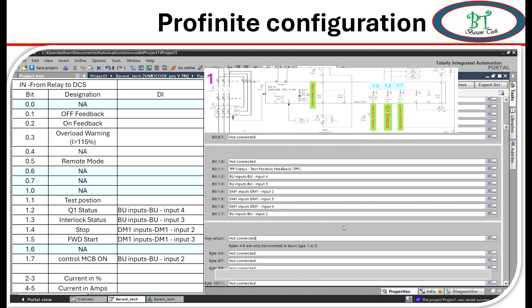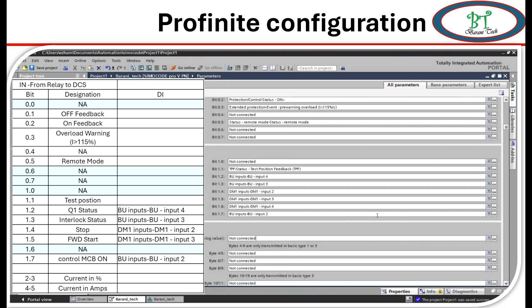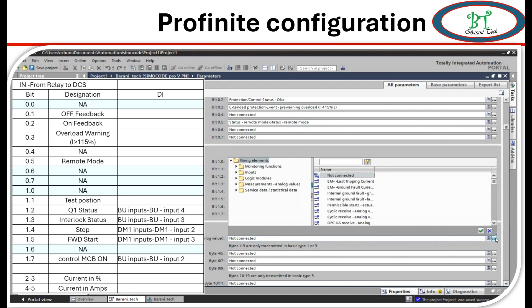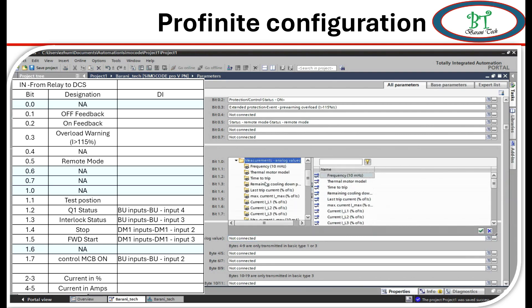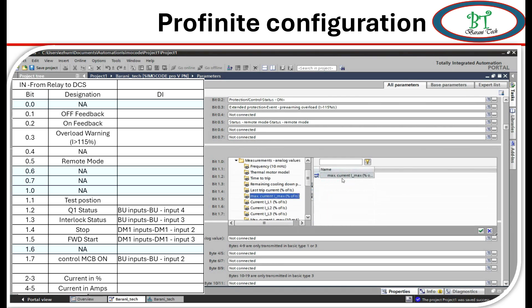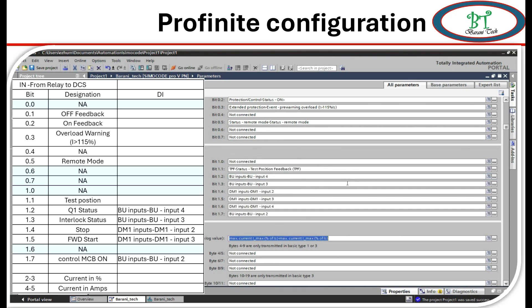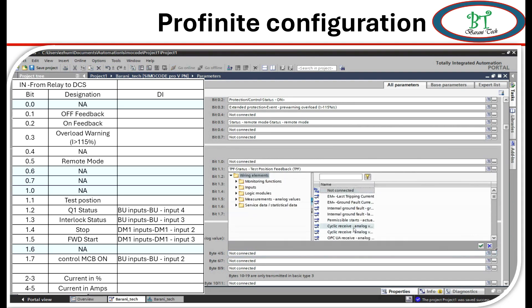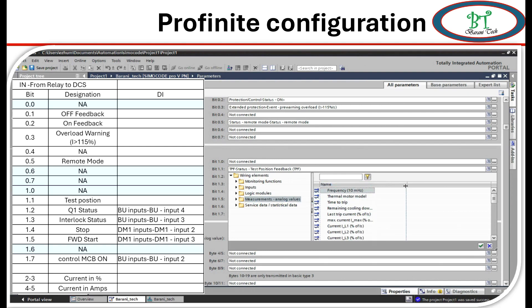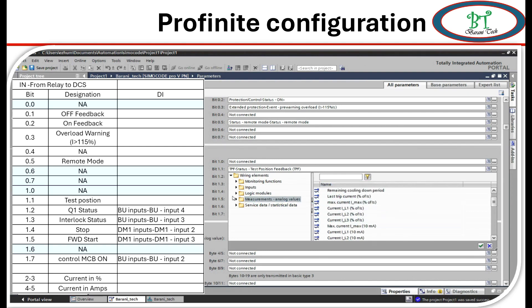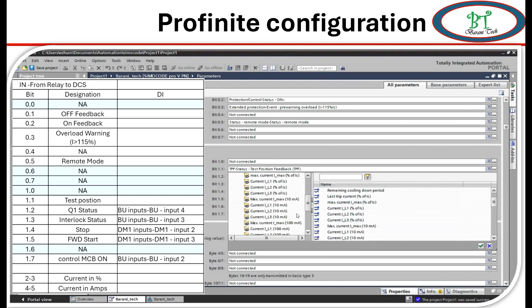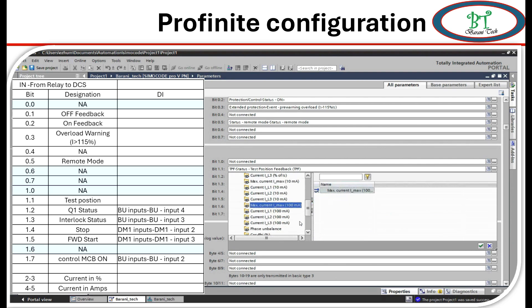Now I am going for analog value configuration. This 2-3 is for measuring current in percentage. So this we need to check on measurement blocks. I go to measurement then I can able to find this maximum current percentage. Yes, we can choose for corresponding signal. Next for 4-5. It is signal for current in magnitude. That is the actual value. So for this I am going to select on measurement on maximum current in amp. So this will be having suitable for this signal.